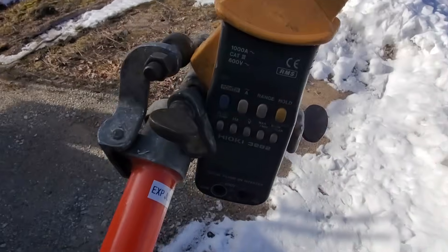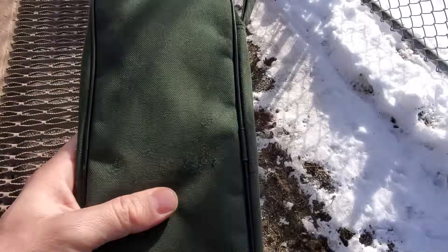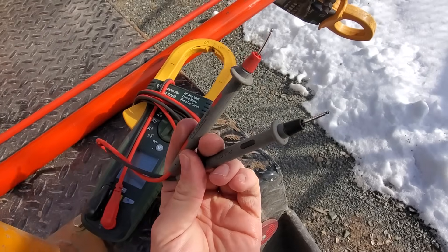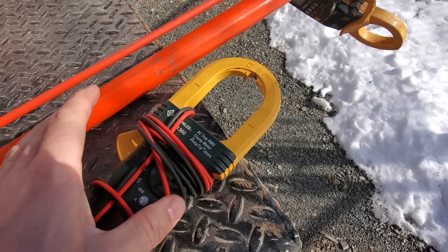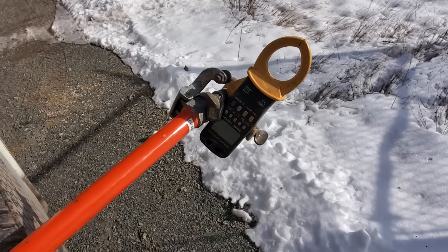I'll get a little pushback on this because there are ammeters specifically designed for high voltage use. This particular ammeter is designed for up to 1000 volts as a multimeter. If you were to stick the leads on 7200 volts, that thing's going to blow up — very dangerous. But with the leads out of the device and just using the clip-on, it's perfectly safe. We do have a tested procedure written up in our standards to be allowed to use this particular ammeter on the high voltage.